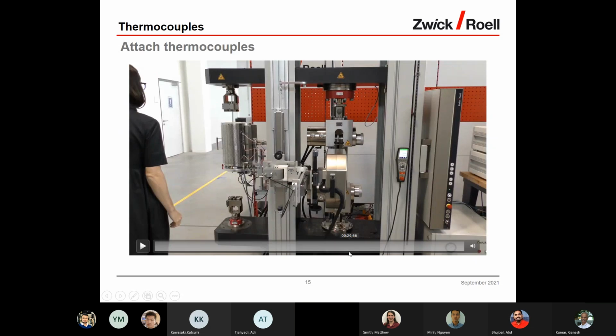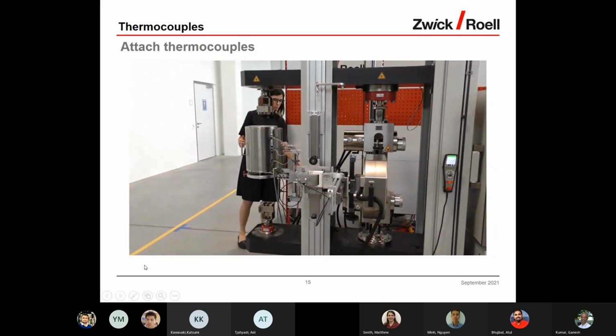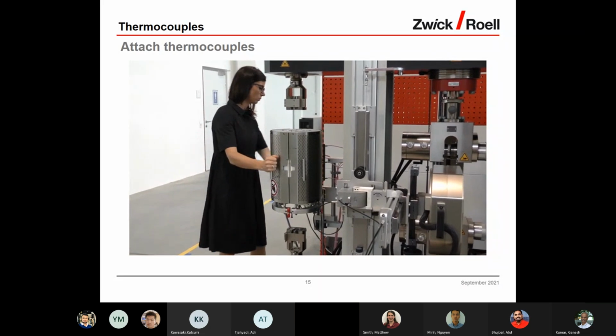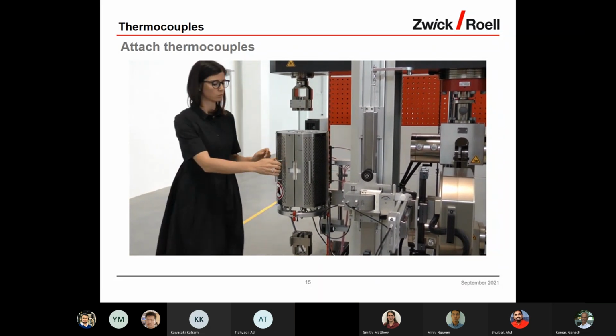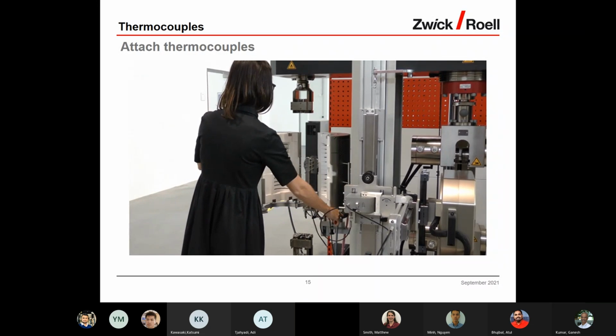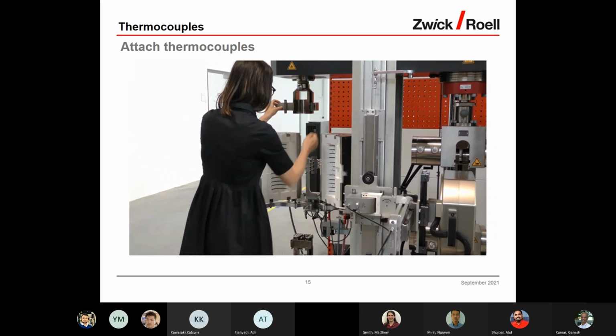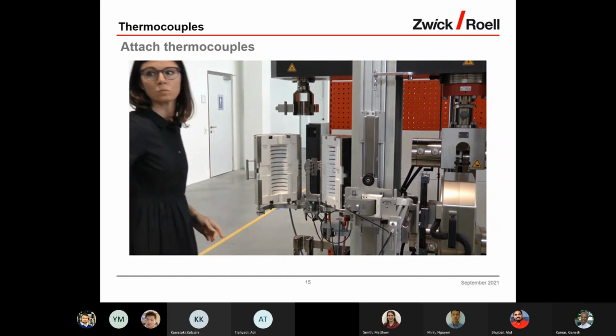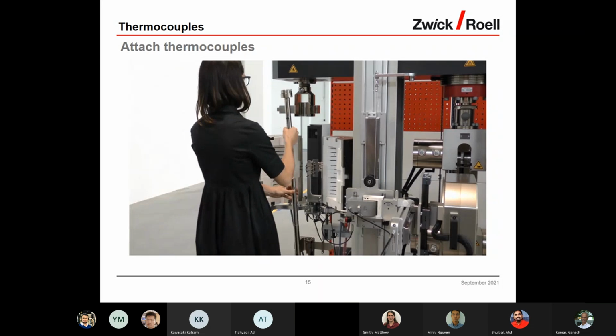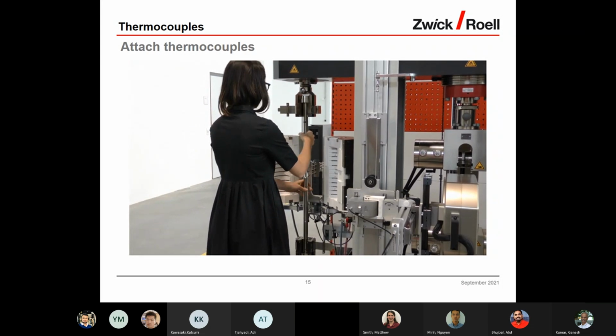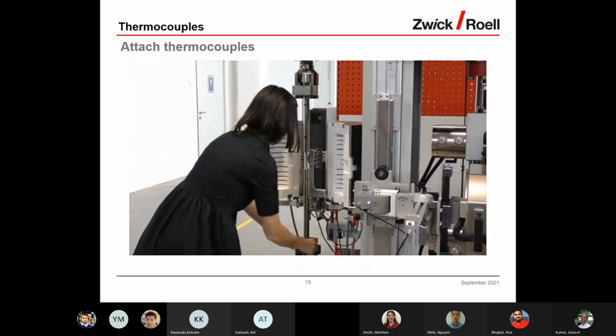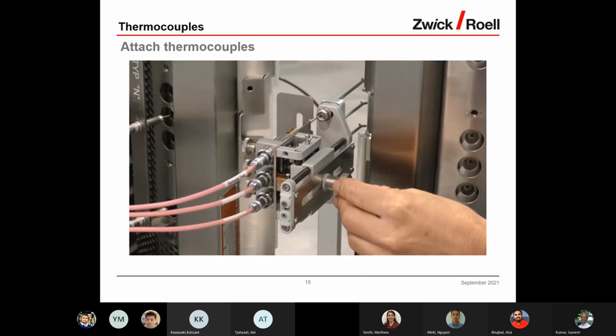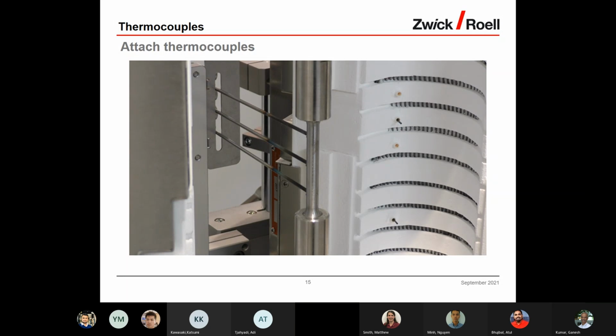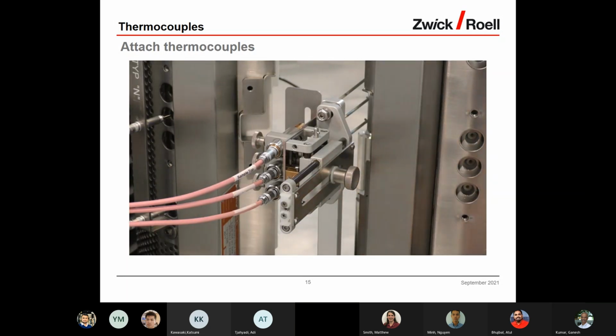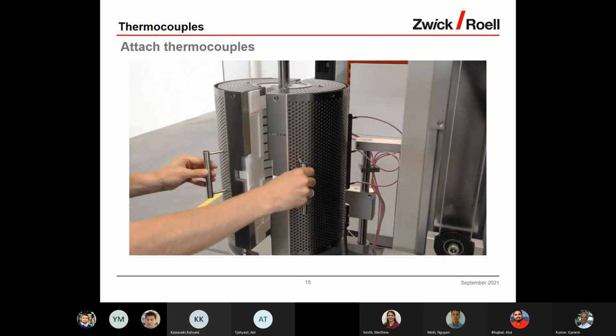Attach the thermocouples. This is also a small movie. Now you can bring the furnace to the center and fix the furnace swivel. Open the furnace. Open the two pull rod couplings, insert the pull rod with the specimen, close the pull rod coupling, open the screw and push the thermocouple unit until it contacts the specimen. And then you also close the furnace.